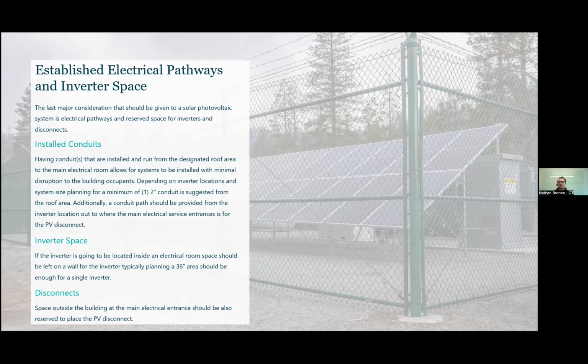Typically, I would say for most of the 50 kW systems, 75 kW systems, we're really only expecting a 2-inch conduit running off that roof for that AC feed out to the outside of the building. But I think it's about working with the electrical engineers and the team on how many paths and how many conduits it's going to require. It really comes down to what that system size is. But generally, what we're seeing is 2-inch conduit down from that roof.